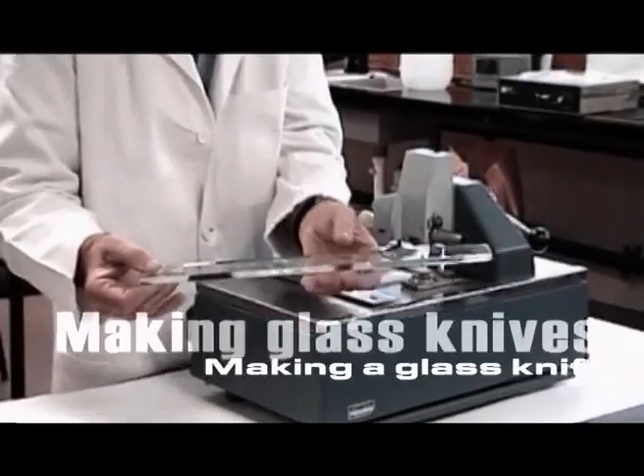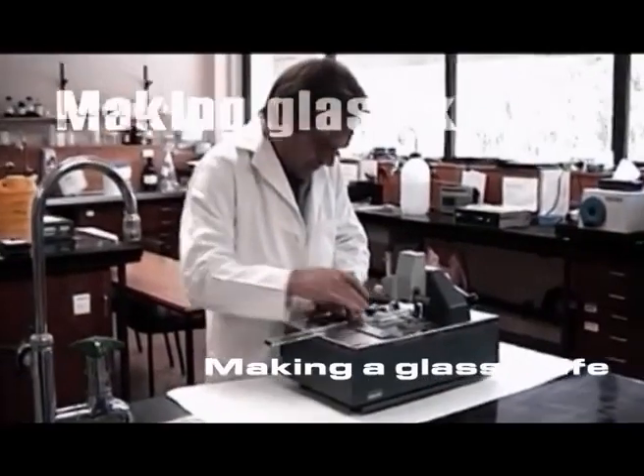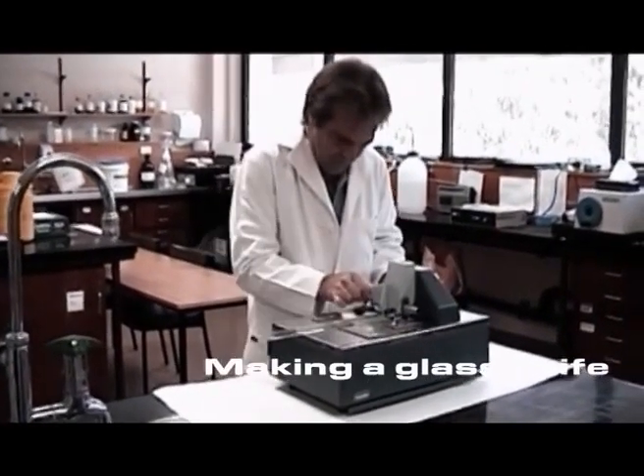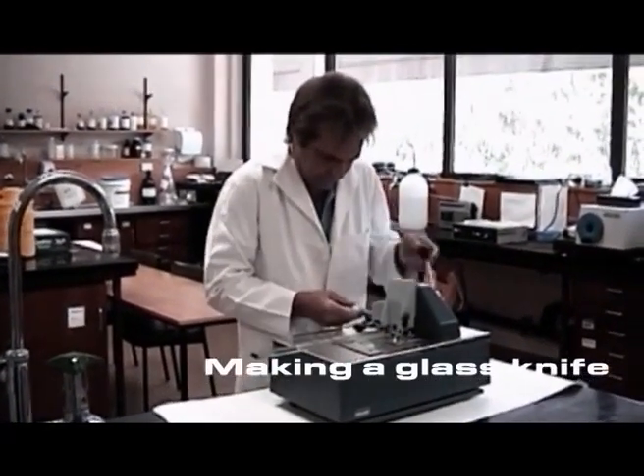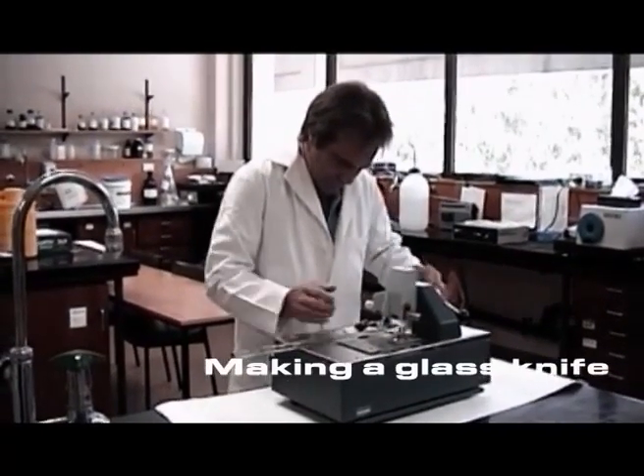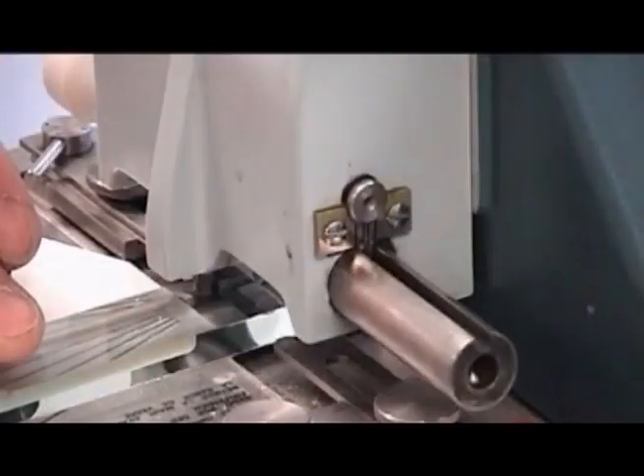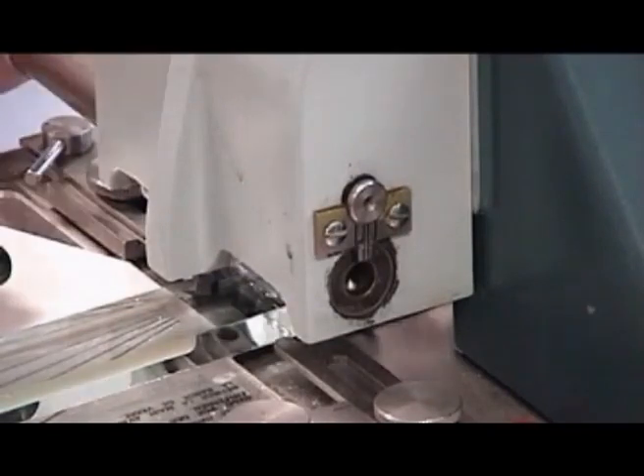Since the resin is very hard, sections can only be cut using freshly fractured glass or a diamond knife. To make a glass knife, a strip of glass is clamped, scored, and broken to form a square. The square is rotated, clamped, scored again, and fractured diagonally to form 2 triangular glass knives.